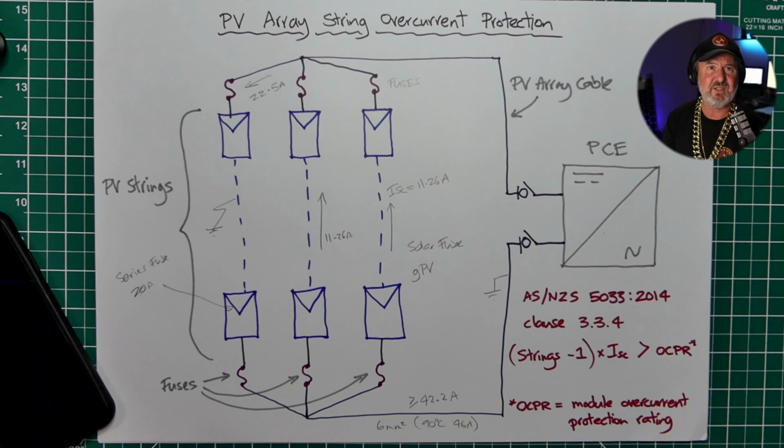How do you actually do this in practice? This is where I'll come back to me for a second. What's a popular option is to use cartridge fuses like these. So this is an HRC fuse switch. Now, anyone who's got good eyes and reviews this afterwards, you'll note that I haven't actually used the right type of fuse in my hand because I couldn't find any in the lab. This is actually a gG fuse, which is for general purpose. Generally, it comes out of my Fluke meter, but it's the same physical size. It's your basically 10 by 38 millimeter fuse size, and this is a fuse holder for such.